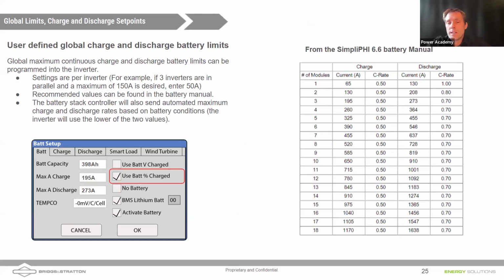On the charge side for these 6.6 batteries, it's a C/2 rate. And that prevents the batteries from getting too hot if we're charging them continuously. On the discharge side, it's a little more complicated because it's actually a 1C discharge rate, but the controller can influence that. These are 130 amp hour batteries. They're typically a little larger in overall capacity than that, but that's the minimum rating, 130 amp hours. So the discharge for a single battery would be 130 amps.